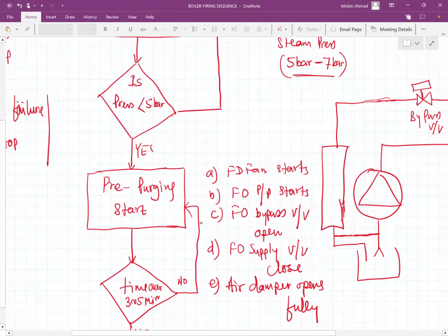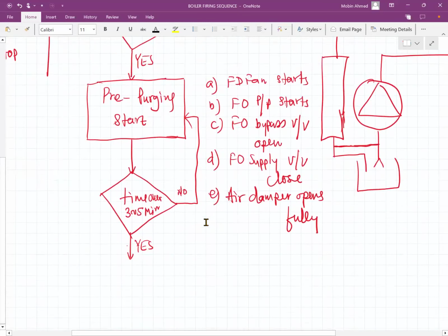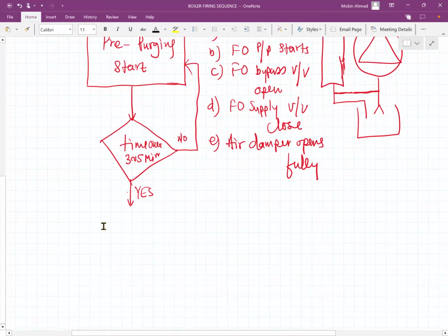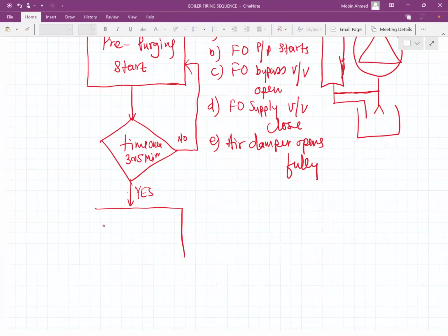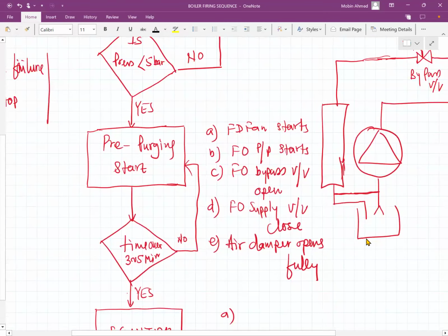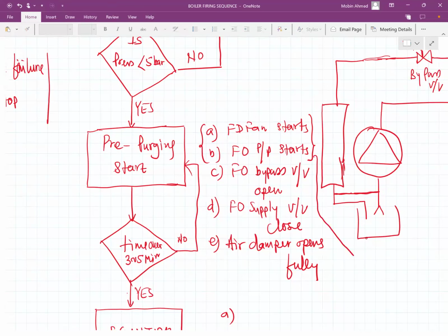Here I must write yes, and this is the no. Now, if the time is completed, then it will go to ignition. Now remember, once the FD fan is started and the FO pump is started, they will continue to run. This is not going to stop till post purging. After post purging, it is going to be off. So I am not writing this again and again. Once started, it will remain continuously running. So I'll just write here, continue to run till post purging.